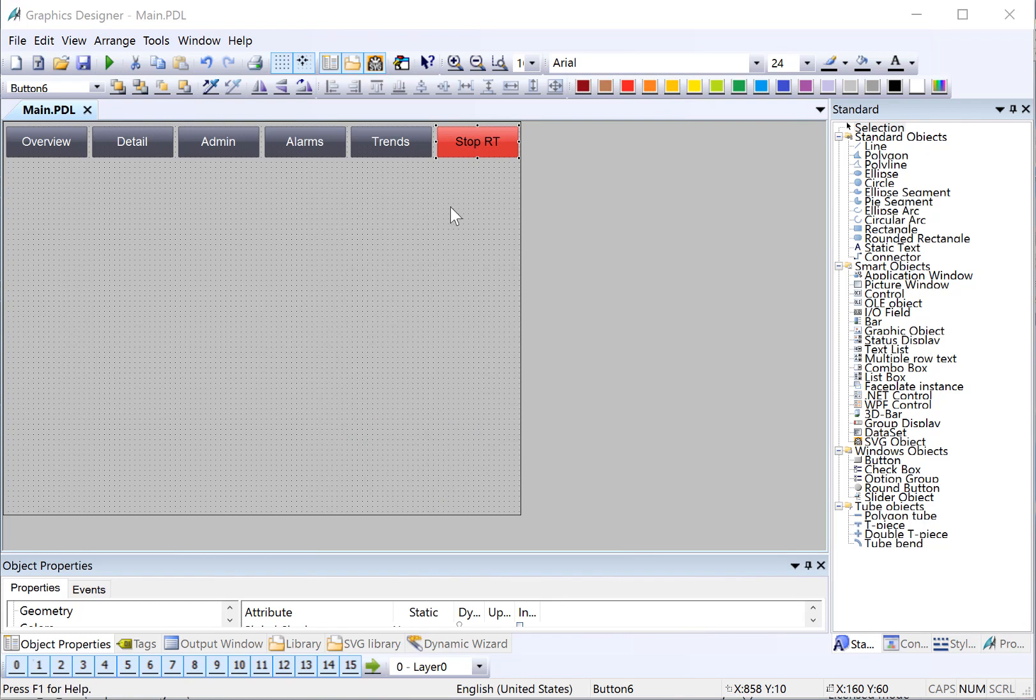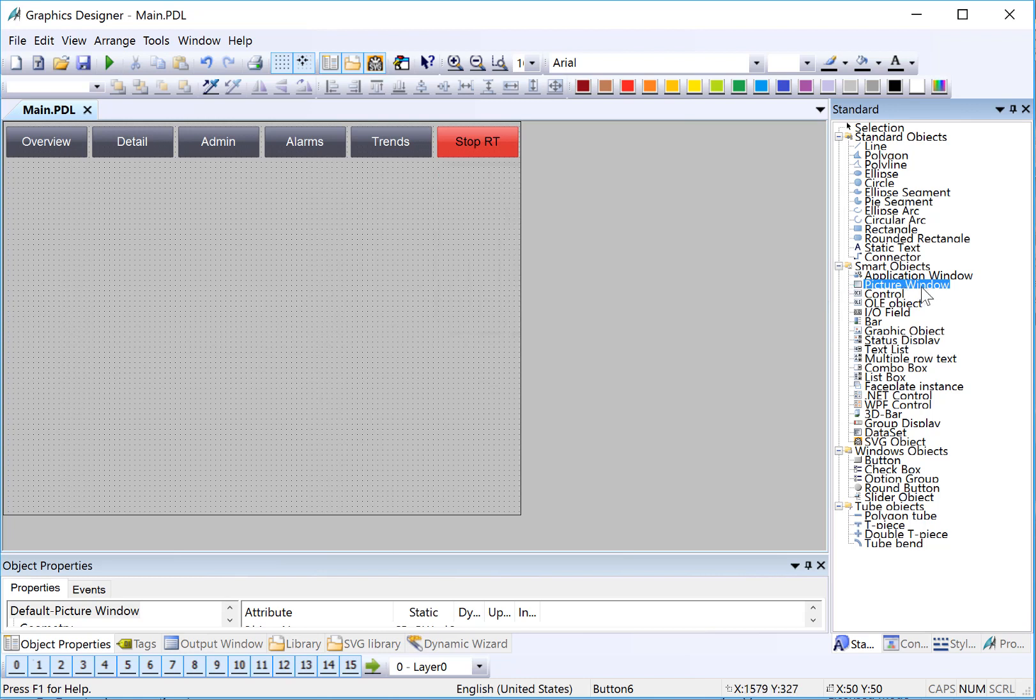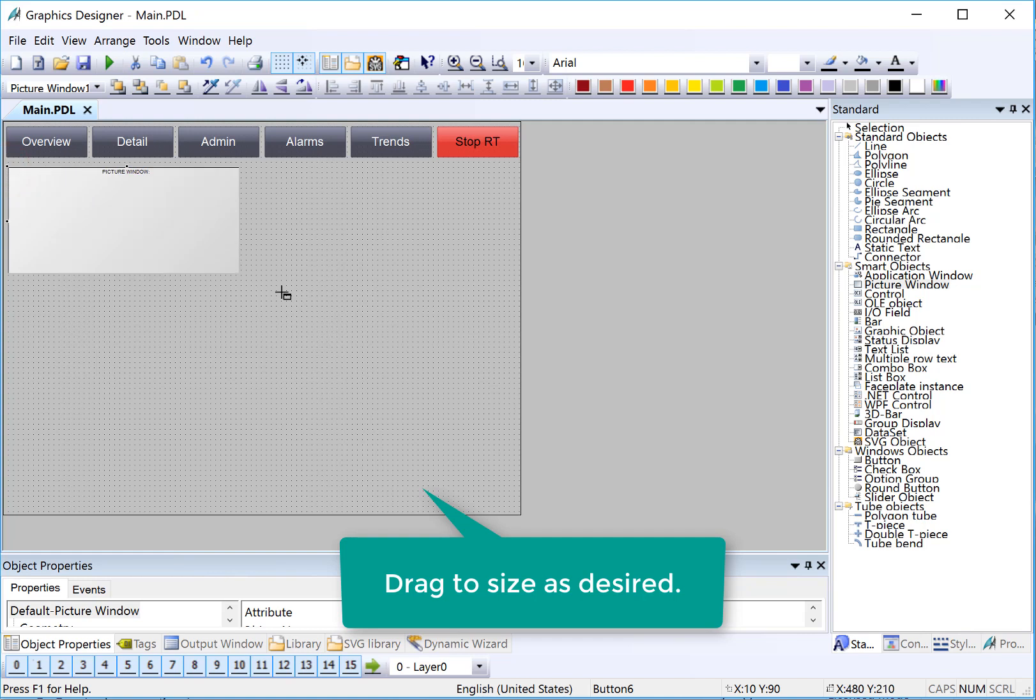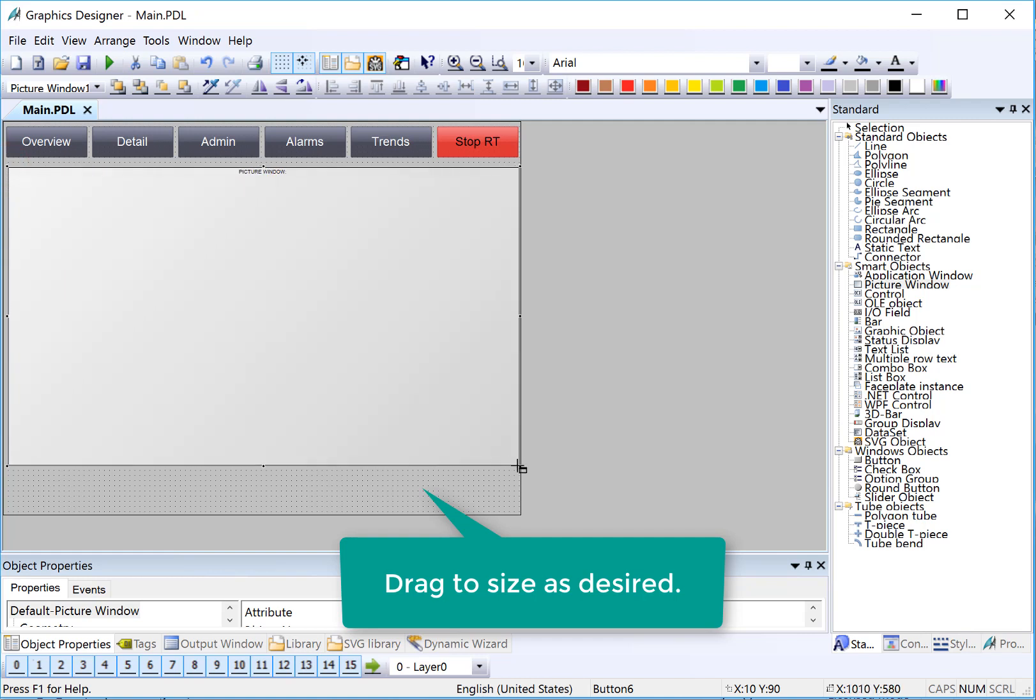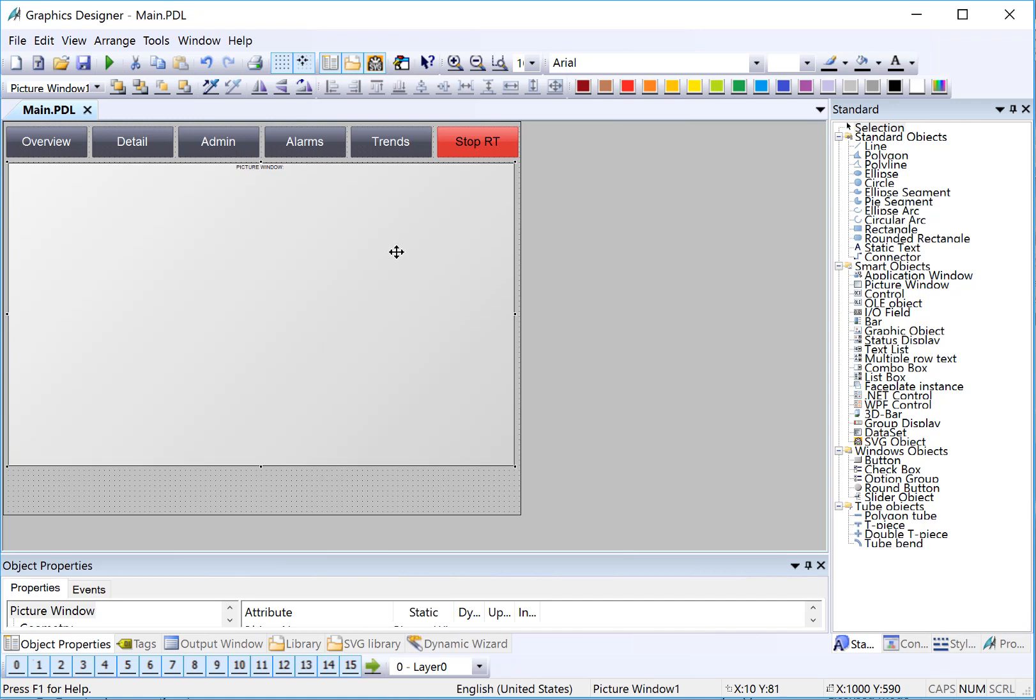Now that I have my navigation buttons in place, I'm going to put a picture window. A picture window is basically like a browser, but it shows WinCC screens instead of web pages. And this is how we can switch which screens the operators are interfacing with. We use a picture window object. So I will click the object. I'm not holding down any mouse buttons. And then I'll find the upper left corner of where I want to put it. I will hold down my left mouse key and I will drag out the picture window to an appropriate size. And of course, we can tweak this a little bit later. And again, I'm going to highlight this picture window object and just use my arrow keys to finally place it where I want.